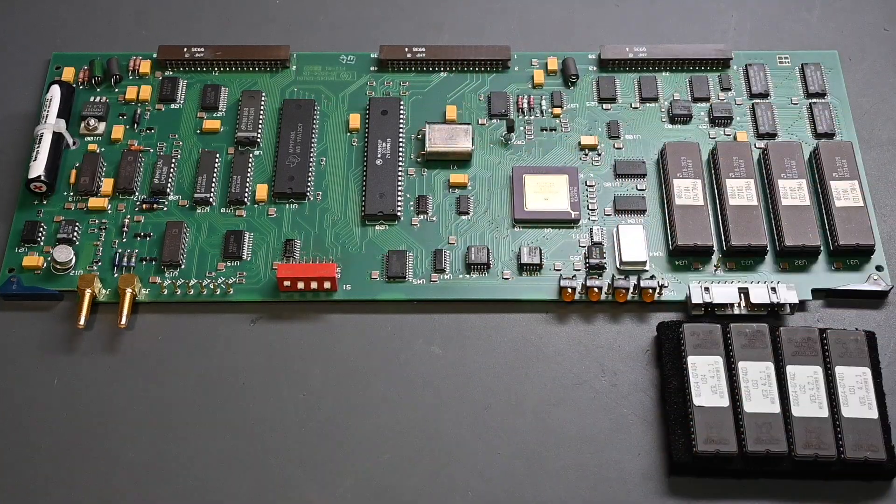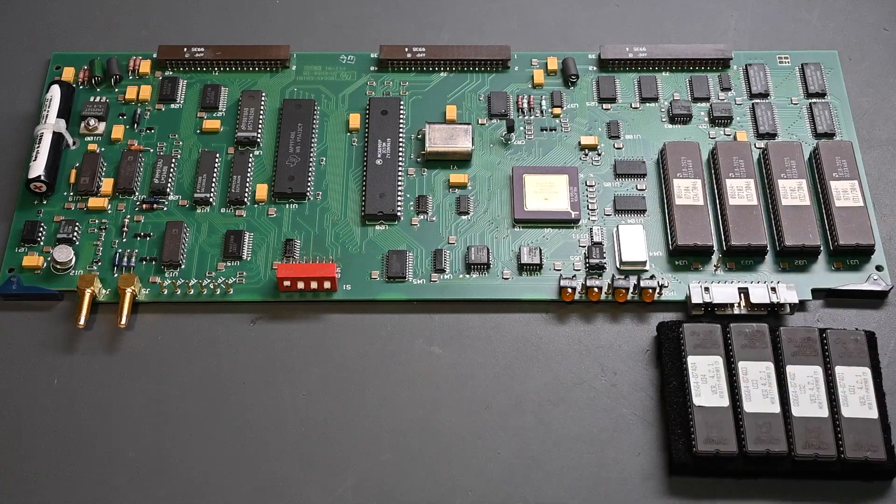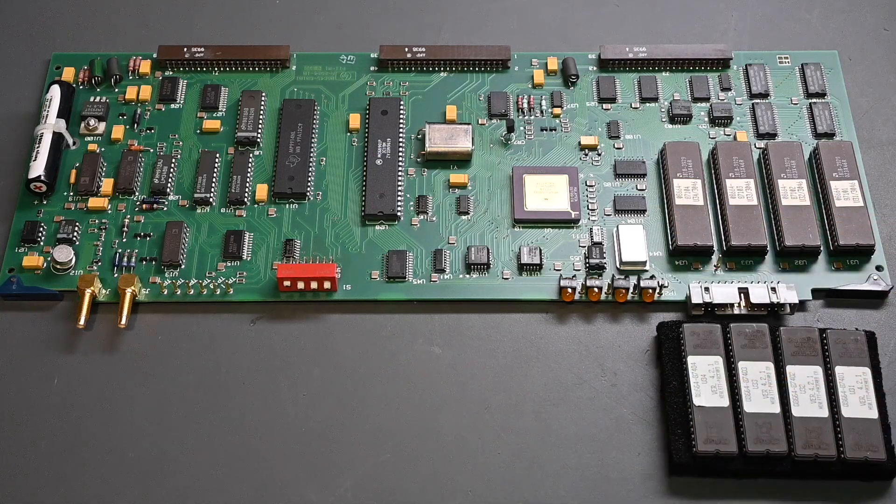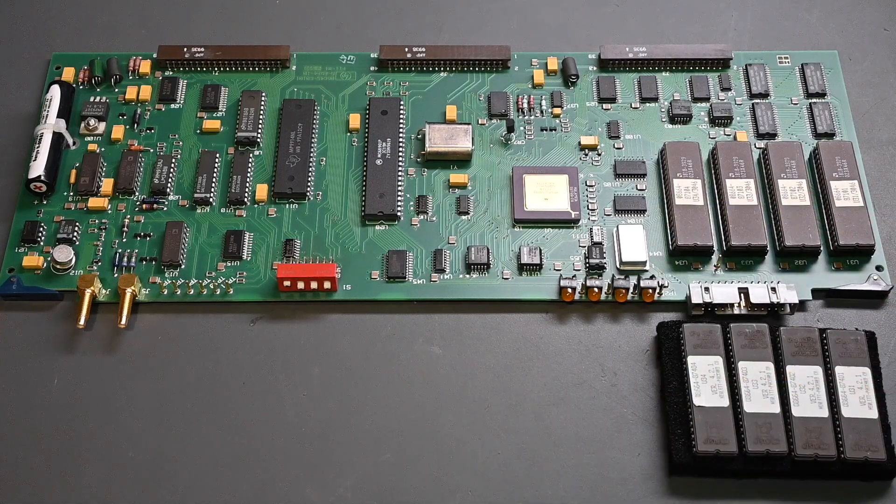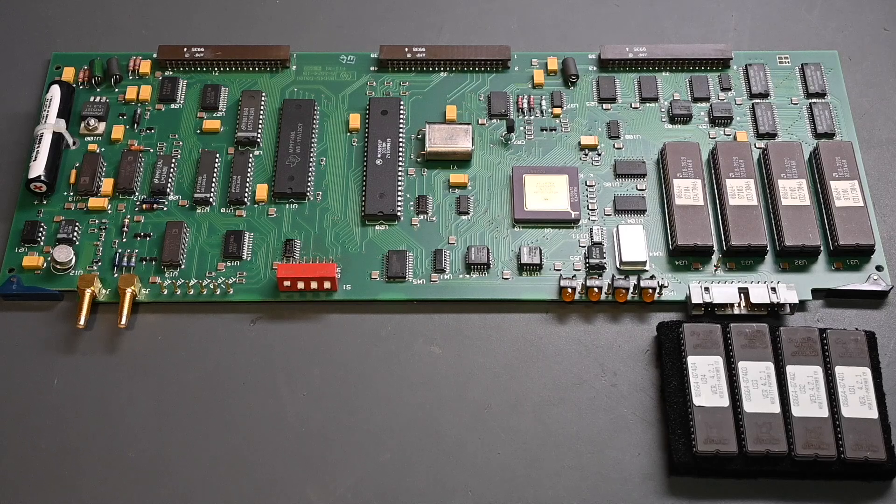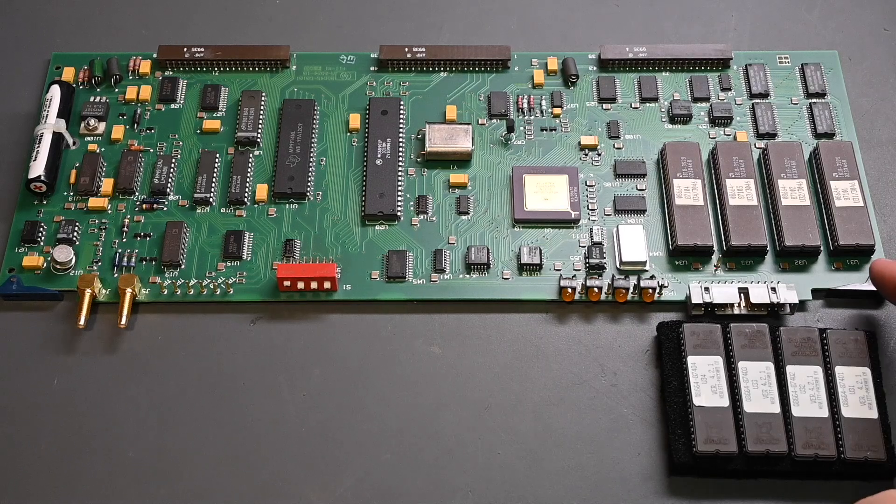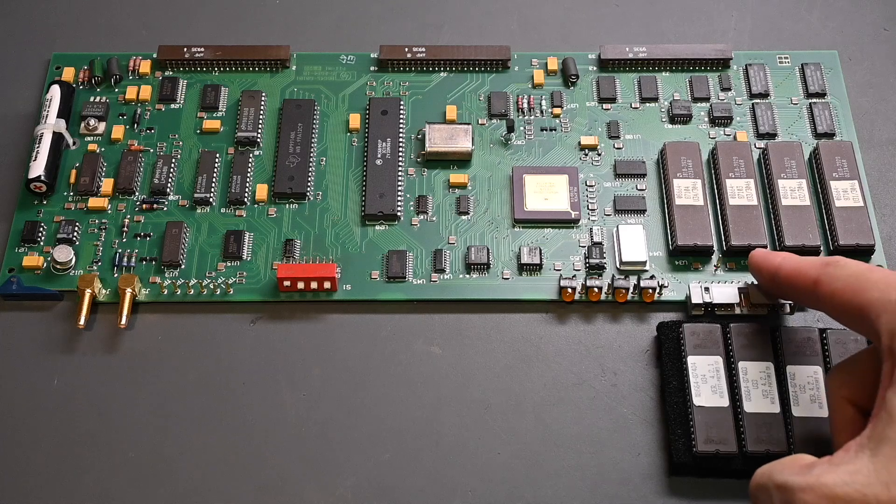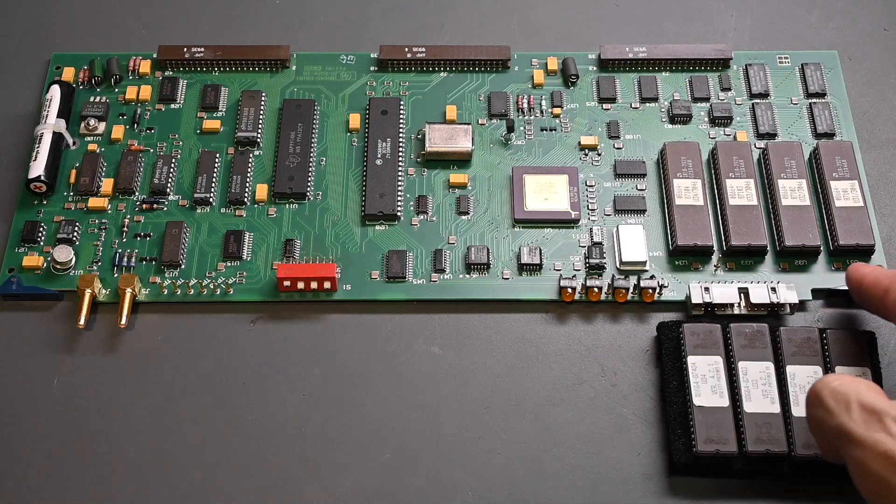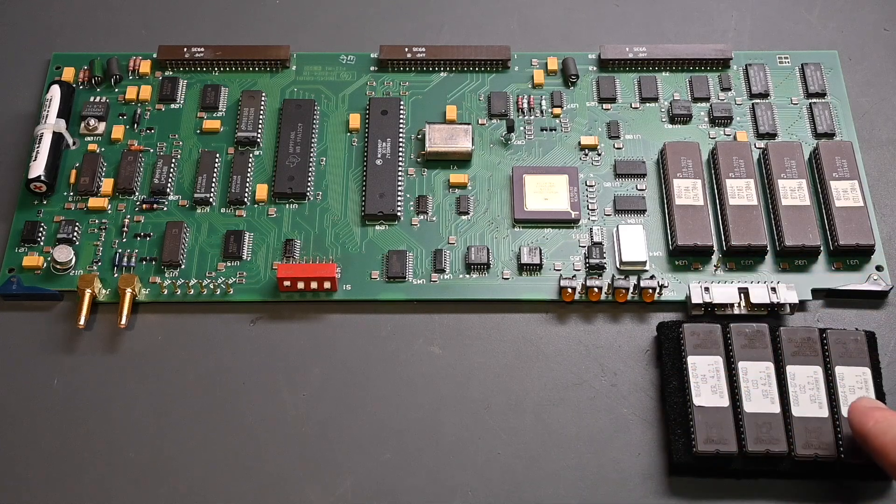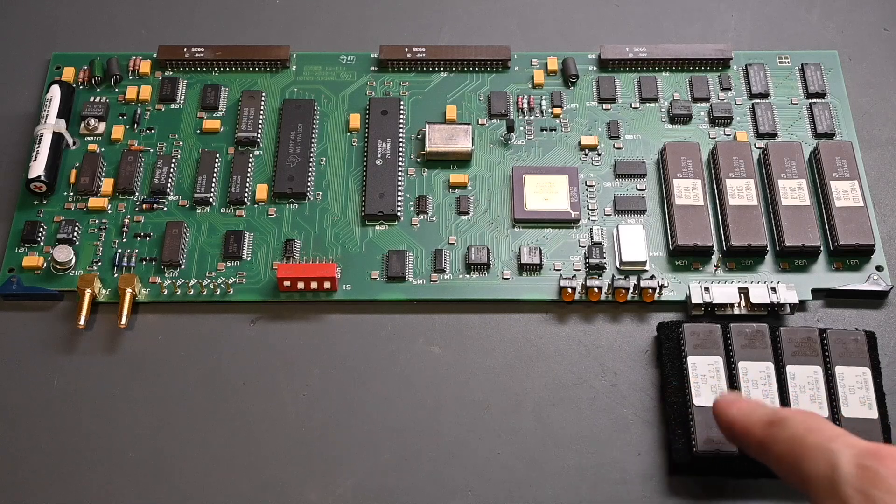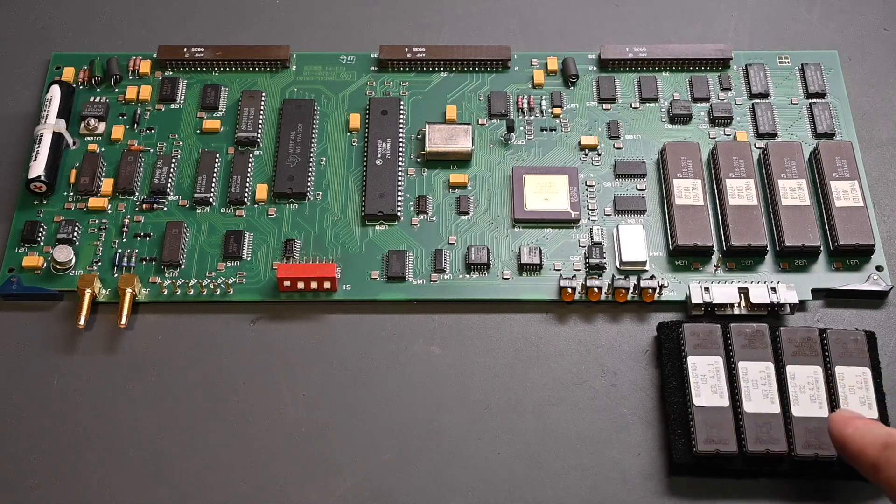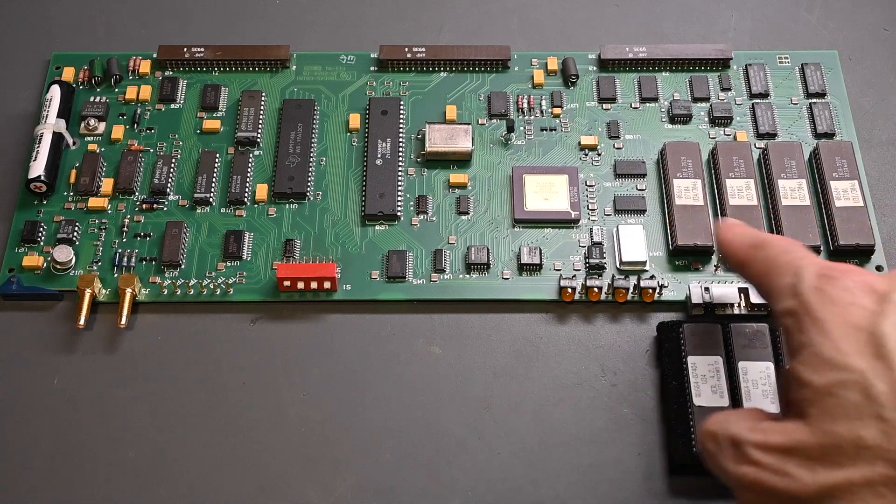All right, control board removed, and I'll get these ROMs moved over to these locations. Of course I'll save the old ROMs because the instrument certainly does work using them, so it makes a safety backup. Right here you can see on the board it says U31, U32, U33, and U34, so those locations that are silk screened on are also marked on these tags right there that are on top of the ROMs, so of course it does matter which position each of the chips is installed.